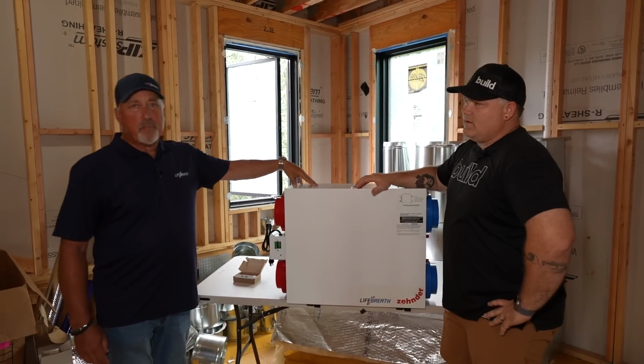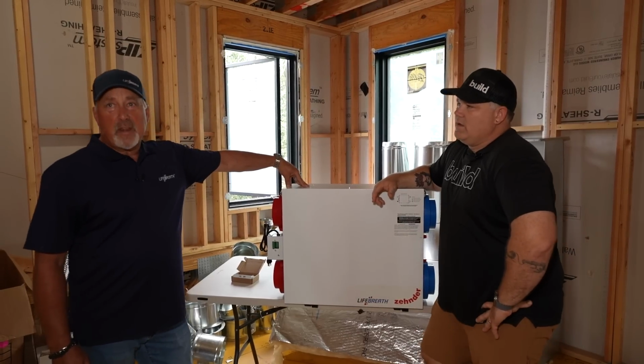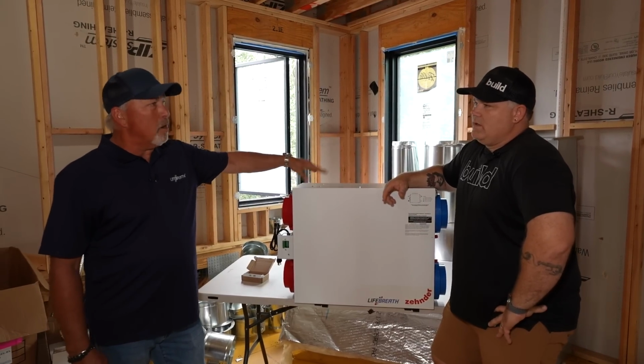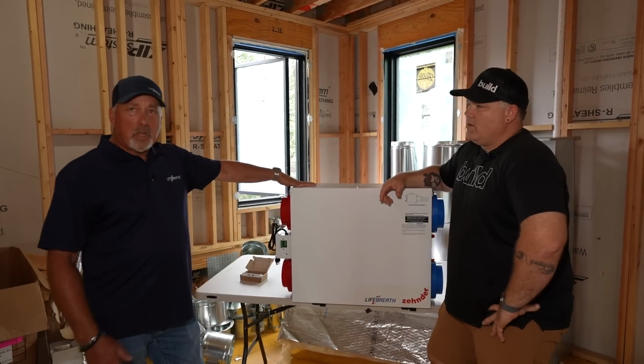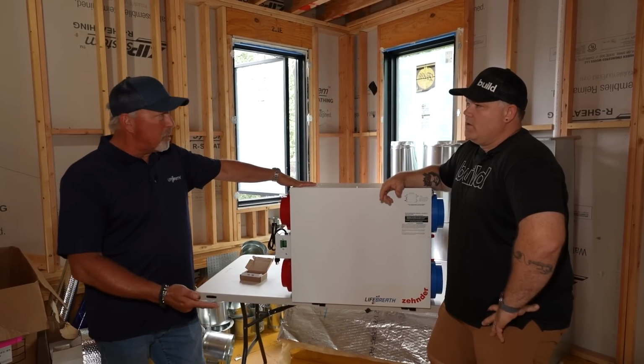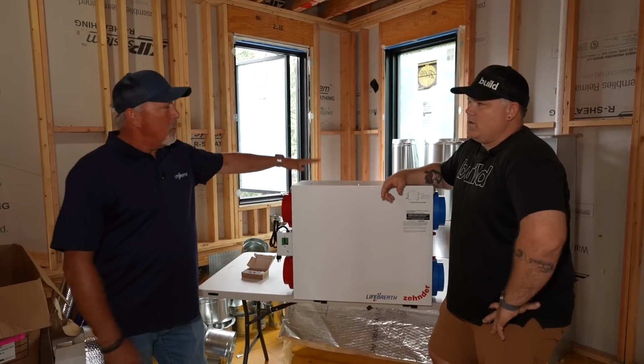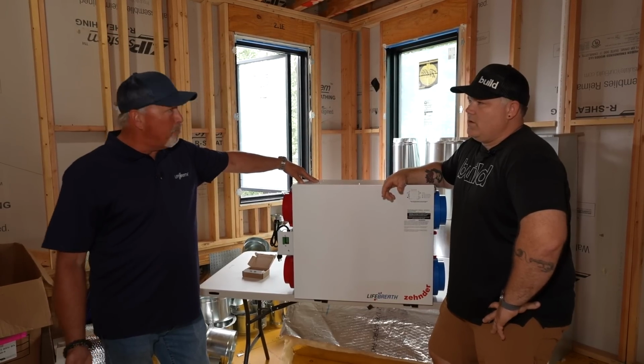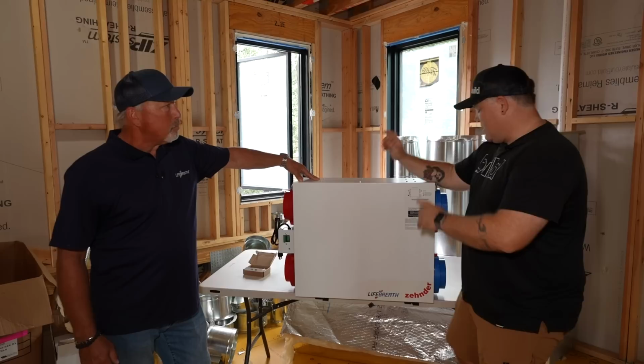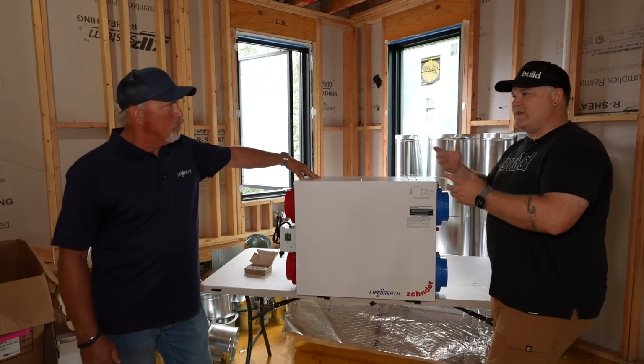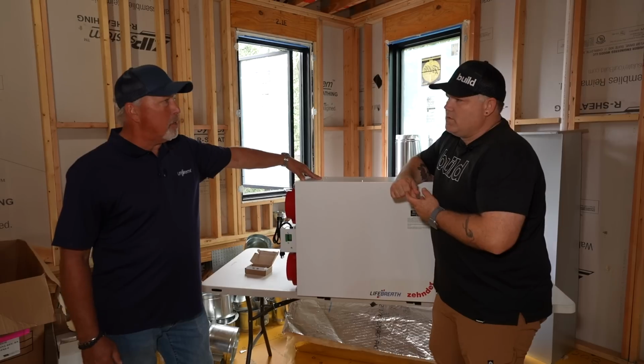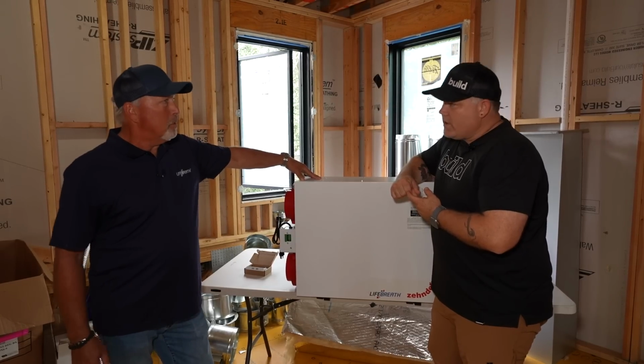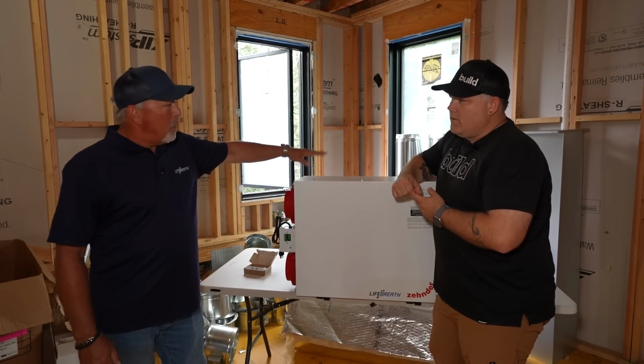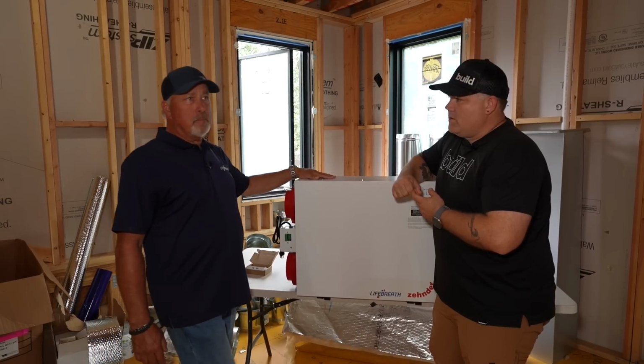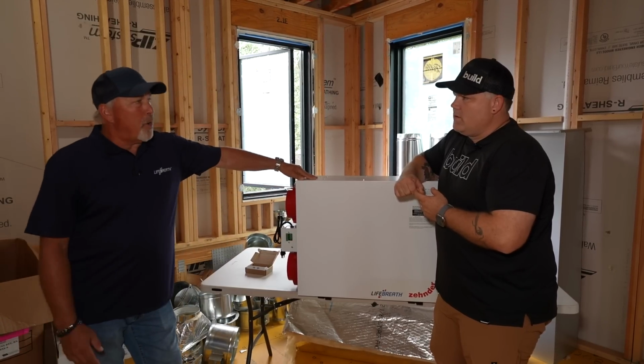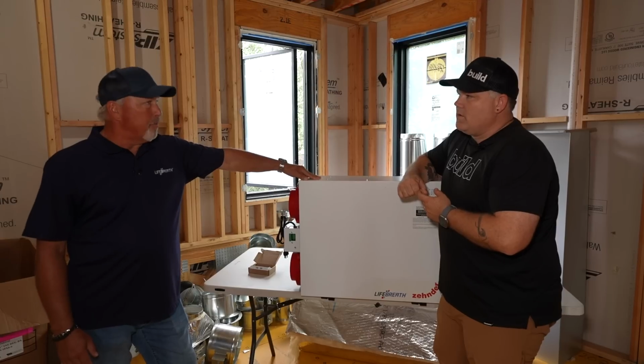I've been with Life Breath for 30 years. For the first 25 of them, I would have never recommended an ERV in your house, ever. Technology has changed - the defrost cycles are much better now, the cores have improved. Now we're getting excellent performance at minus 25. No, it's actually just based on the core itself and its defrost - our defrost has got great control. When I talk to the other old guys in my company, we're hard pressed now to find a location for an HRV over an ERV.